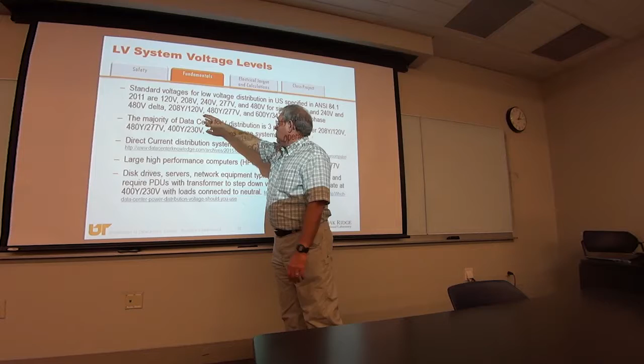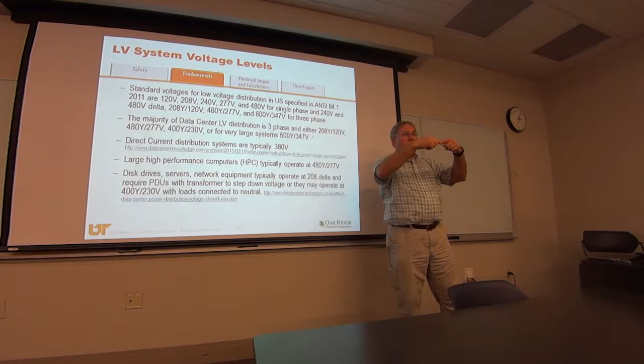But typically in a majority of data centers, we'll see 208 Y 120, or they'll see 480 volt Y 277. Now that doesn't mean you've got Y loads. It just means the transformer can take Y loads. You may just have a 3-phase load, in which case it would be a 3-phase 208 volt. A lot of the PDUs in your cabinets that you plug into, the things under the floor, will be 3-phase 208 without a neutral. So they go 208, 208, and 208, right? So all your equipment is rated for 208.